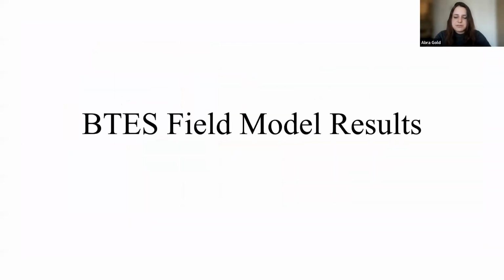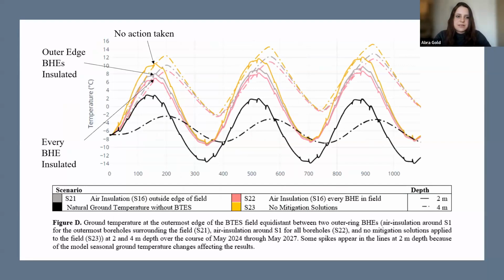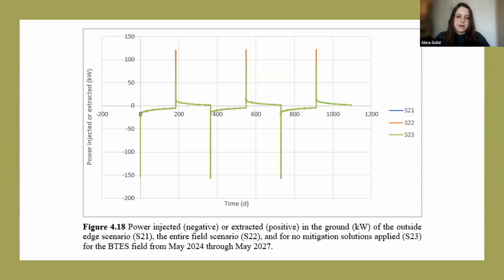And this is the BTES field model results. So it turns out that insulating every BHE in the field, at the outer edge of the field, that's what this graph is for, it's ground temperatures. Insulating every BHE is much more effective than insulating the outer BHEs just along the edge of the field, or not taking any action at all when it comes to preventing the ground from warming any more than it would naturally. And then the power injected and extracted was once again showing negligible differences between scenarios in this model.